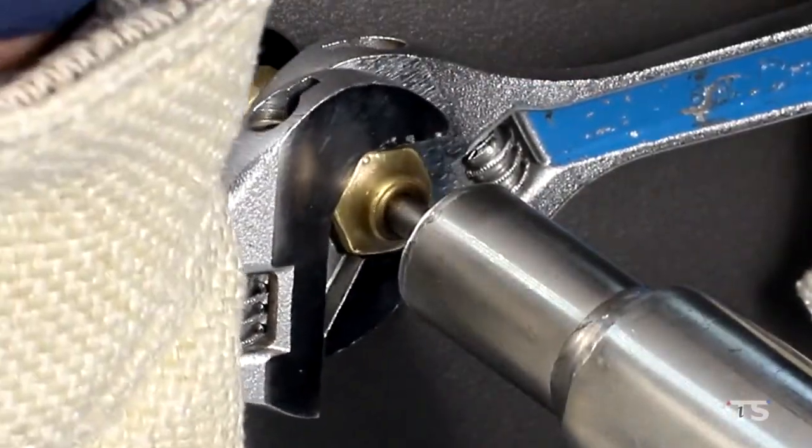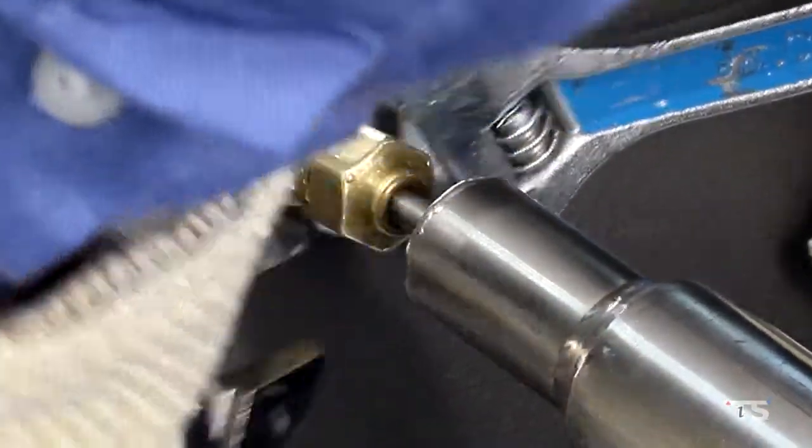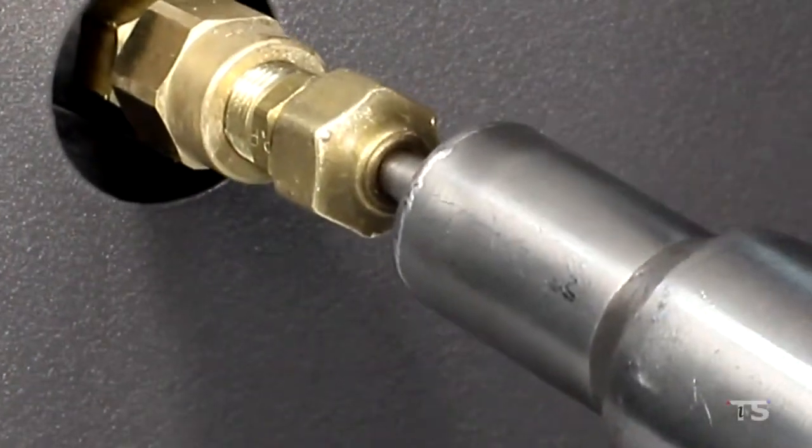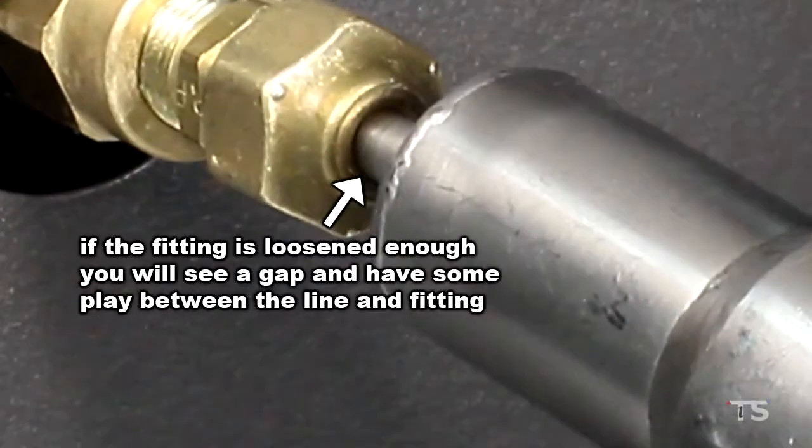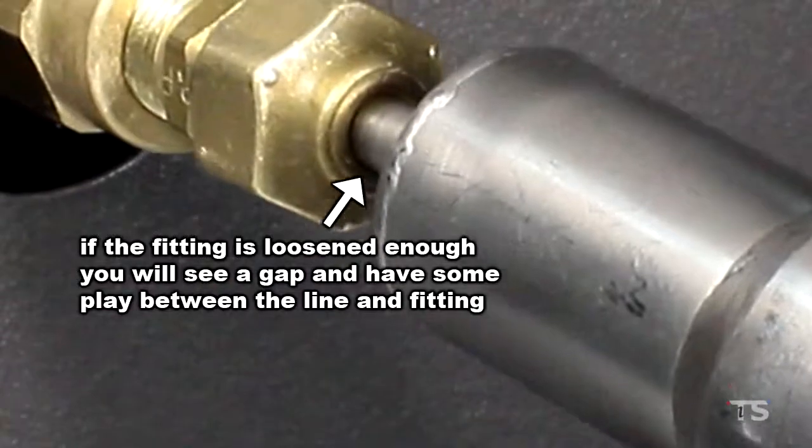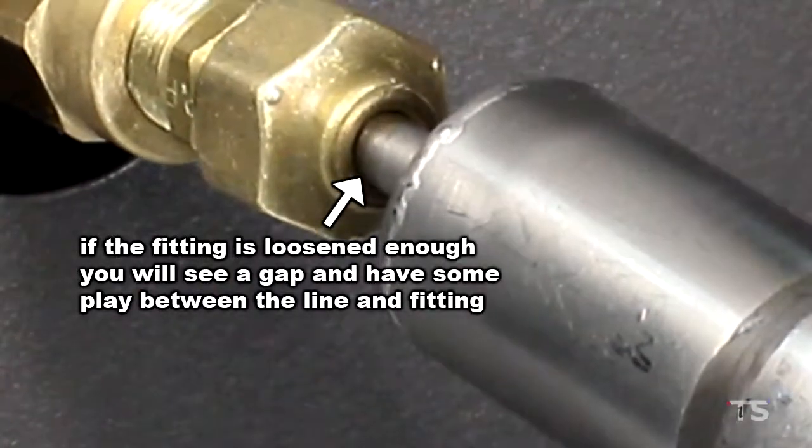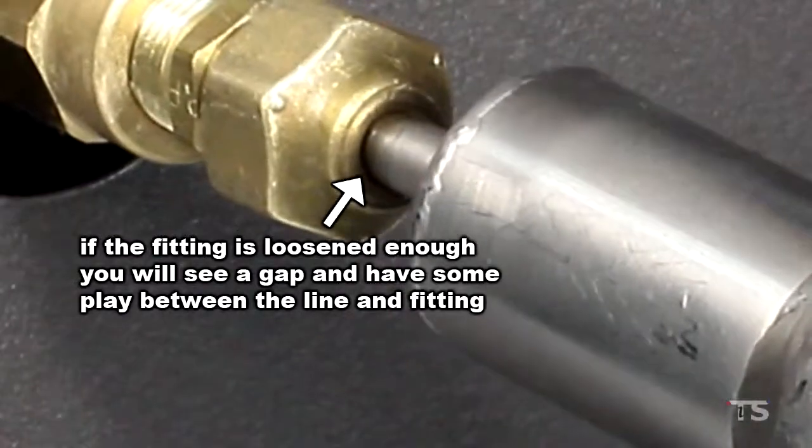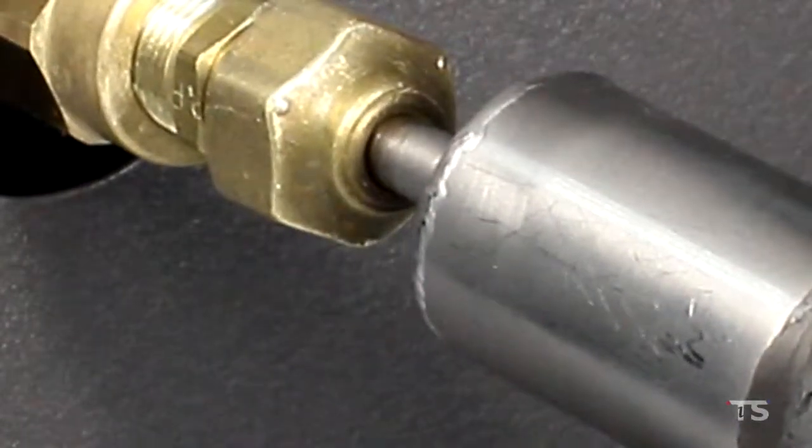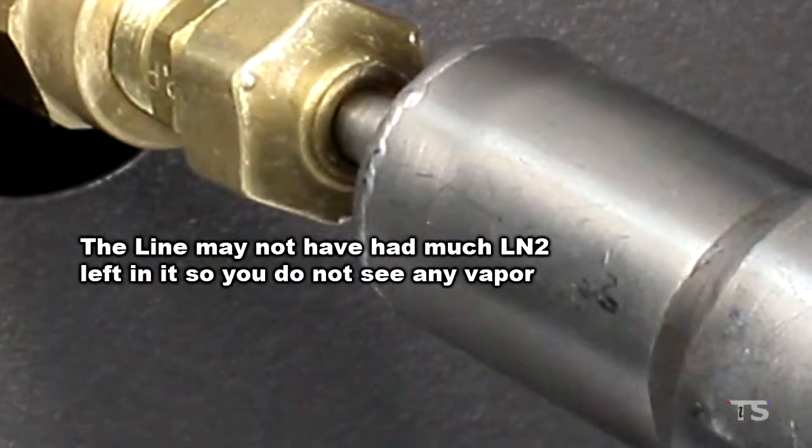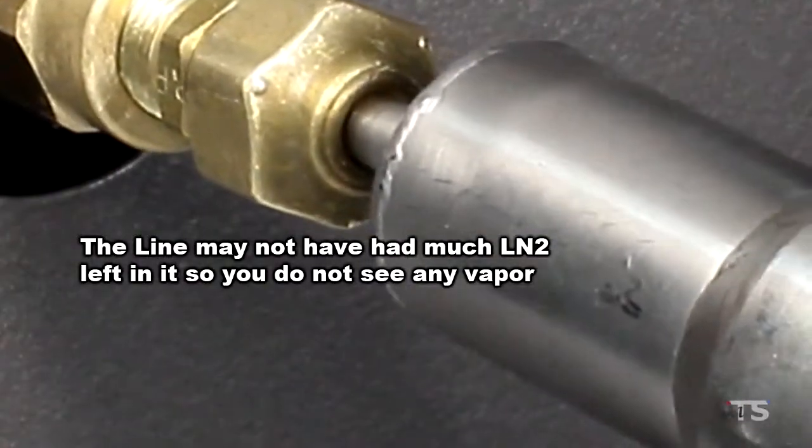If you don't see vapor, that could be okay. Just look carefully at the back of the flare fitting of the delivery line. If this fitting is loosened enough, you will see a gap and have some play between the flare fitting and where the delivery line passes through the fitting. This gap is where the vapor would escape from, and if you see the gap but no vapor, then the line may not have had much LN2 in it to begin with.